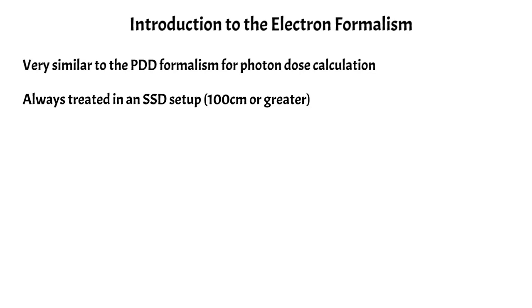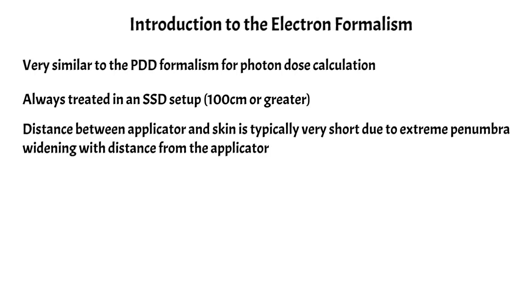And often they are treated at extended SSDs due to potential collisions that the patient may have with the applicator. We want to really minimize the distance between the applicator and the skin because the farther the skin is away from the tip of the applicator, we get extreme penumbra widening, so we're getting dose outside the field. That penumbra widening is typically caused by electron scatter, so electrons are very sporadic and change their direction easily.